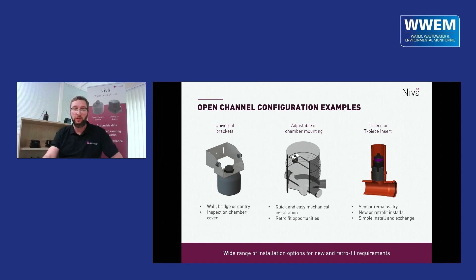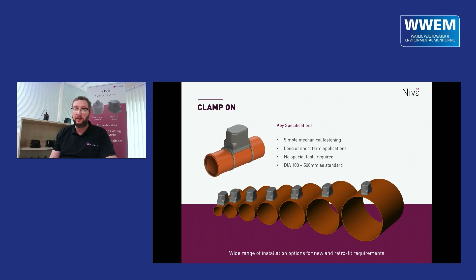The clamp-on version of Nivå needs to be pipe-specific, which allows the curve on the bottom to match the curve of the pipe. Minimal special tools required for this. There's no acoustic paste, special cements, or anything like that. A few options for fitting, and I'll talk about commissioning in a minute, but the easiest is to take a couple of steel tie wraps, get them around the pipe, and pull it tight. Currently, we're supporting pipes from 100 to 500 mil, plastic pipes only at the moment, but we think we could go beyond that if there's a clear market need.